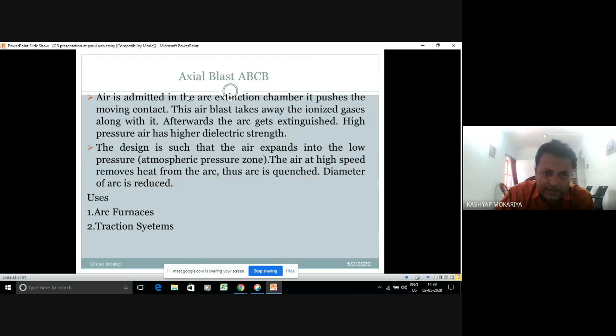In an axial blast circuit breaker, air is admitted in the arc extinction chamber and pushed through the moving contact. This air blast takes away the ionized gas along with it. Afterwards, the arc gets extinguished. High pressure air has a higher dielectric strength. In this design, the air expands into the low pressure. The air at high speed removes heat from the arc. Thus, the arc is stretched and the diameter of the arc is reduced.